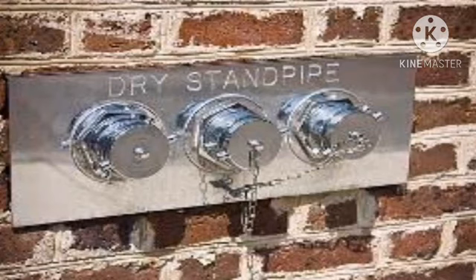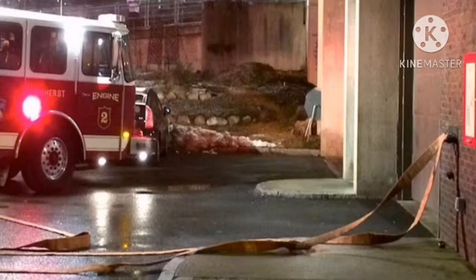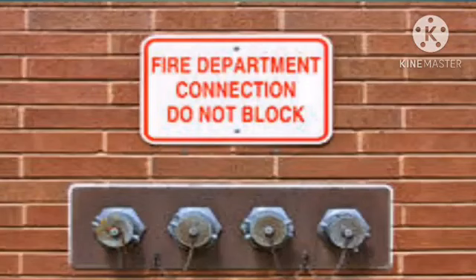Fire department connections. Fire department connections are utilized by the firefighters on the scene to either supply water to the standpipes or supplement the building's already existing water supply. This additional water can be sourced from the fire truck itself or from a hydrant that can tap into the water the building's standpipes may not have access to. These are usually included in the initial creation of the standpipes in order to provide an extra source of water to the building.